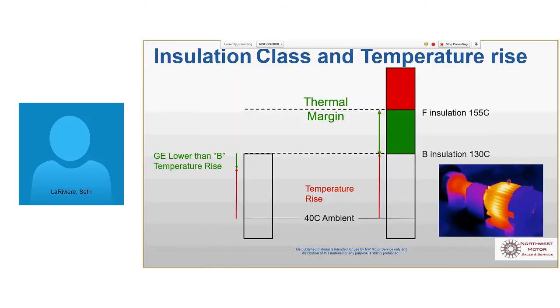So as we were talking a little bit about that IEEE 841 specification, that specifies a Class B temperature rise and a Class F insulation. So motors are rated, they have a rise, which is the heat they create when they're operating and producing horsepower. That's the temperature rise. The temperature insulation limit is what the designer has built into that motor, how much heat it can take. So by convention, that IEEE 841 standard says a manufacturer has to build into their motor insulated quality windings up to 155 degrees C. That's a Class F limit. And it has to run at a Class B, which is 80 degrees of rise or 130 total. We'll get into that in a second.